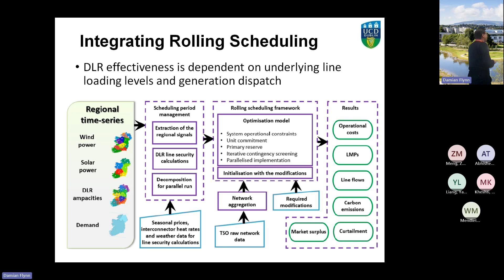So what we wanted to do was assess this for the Irish power system, thinking about the natural loading of individual lines. If it's windy, yes, we can increase the rating, but at those particular times, is that line going to be heavily loaded? You need to bring in a unit commitment phase, because on a really windy day, a lot of your conventional generation will be offline, which affects the power flows. If it isn't windy, the conventional units will be on, in different locations, which affects the power flows as well. So it's not just where it's windy, it's what the prevailing power flow and level of power flow will be in that location.